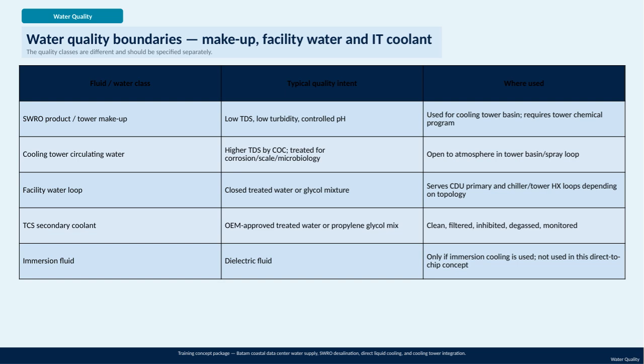Here, we have several distinct water classes, each with its own quality requirements because they serve different functions. First, the SWRO product or tower makeup water needs to have low total dissolved solids, low turbidity, and controlled pH. This is essential because it feeds the cooling tower basin and needs to be compatible with the tower's chemical treatment program. Next, the cooling tower circulating water naturally has higher TDS due to cycles of concentration, but is carefully treated to prevent corrosion, scaling, and microbial growth. This water is open to the atmosphere, circulating through the tower basin and spray loops.